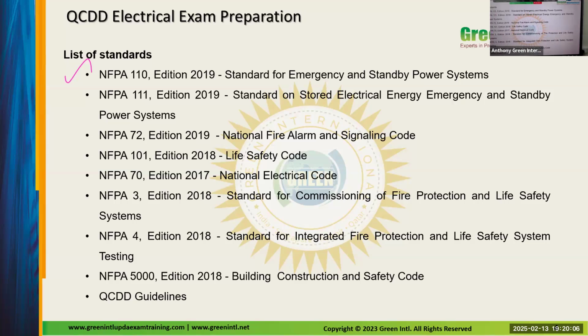There are 3 types of light fixtures. One is the emergency exit, or sometimes the light fixtures have a battery backup. Wherever you see battery backup or emergency exit, there is definitely a 3 hour battery backup mentioned. That's related to NFPA 110... actually, since it's stored energy, the normal light fixtures are not related to that code. For emergency light fixtures with the 3 hour battery backup, we need to refer to NFPA 111 edition, because it's related to stored electric energy.